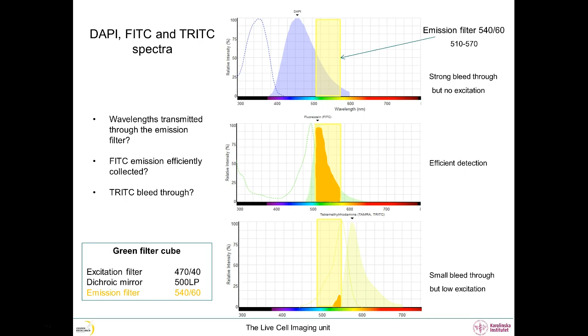We also see that the TRITC signal bleeds through this filter a little bit. We have seen before that TRITC is inefficiently cross-excited by our excitation filter, and we see here that the bleed-through is rather small. So we expect the emission that reaches the detector to be quite weak. We have now identified that the FITC filter cube leads to both cross-excitation and bleed-through of TRITC, but at a low level.